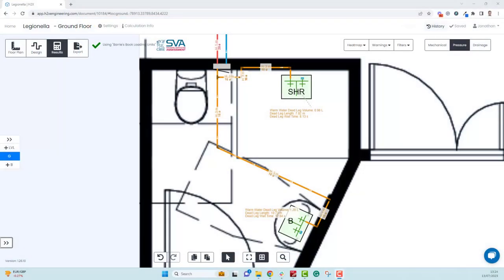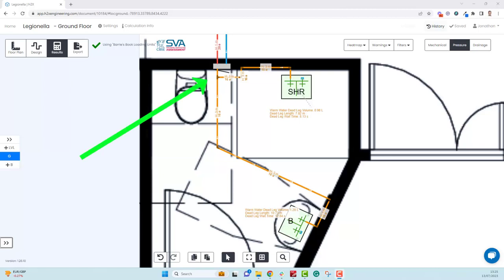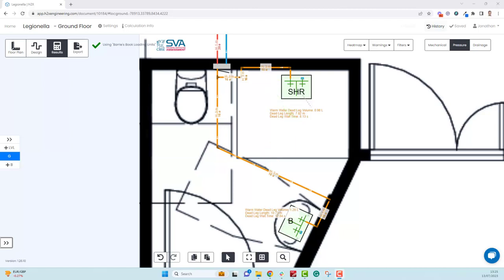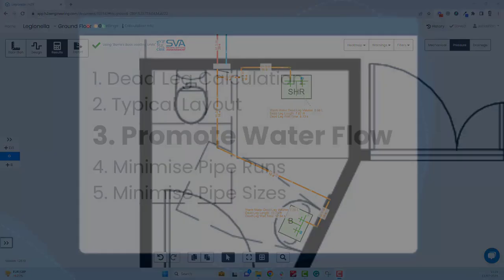Next, we'll take a look at a typical room layout for an ensuite, which you'll find very common in countries like Australia. You'd have the TMV centrally located to the room about one to one and a half meters above the floor. The pipes would then branch off to supply the different fixtures. It typically runs about three meters above the ceiling, then drops down to about one meter in the wall to connect to the fixtures. While this design layout works, there is room for improvement from a legionella aspect.